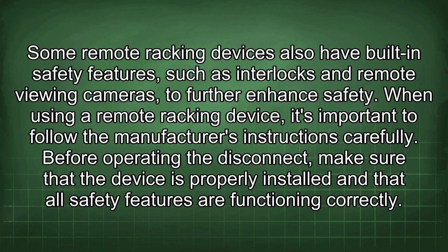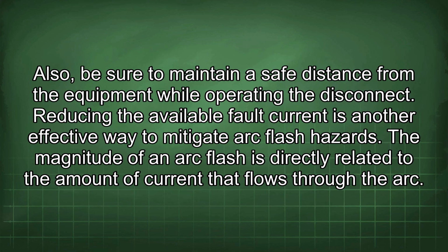Some remote racking devices also have built-in safety features, such as interlocks and remote viewing cameras, to further enhance safety. When using a remote racking device, it's important to follow the manufacturer's instructions carefully. Before operating the disconnect, make sure that the device is properly installed and that all safety features are functioning correctly. Also, be sure to maintain a safe distance from the equipment while operating the disconnect.